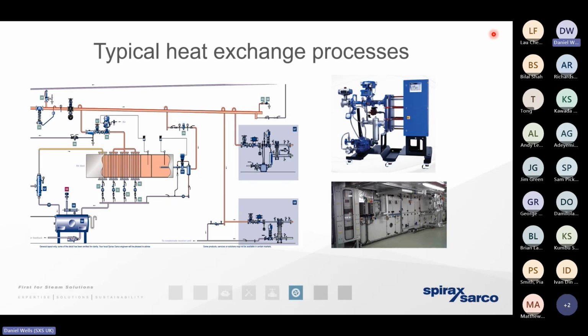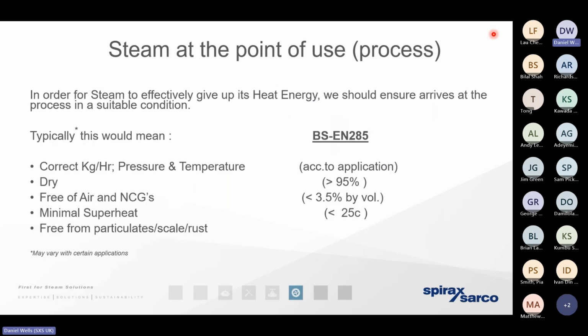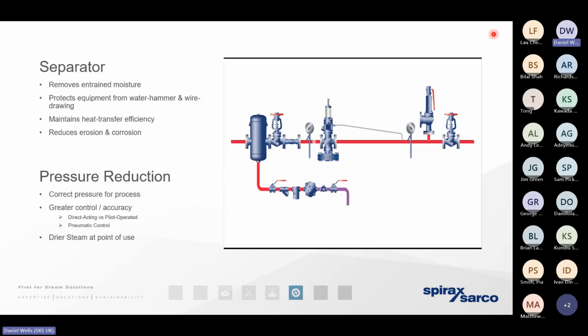More likely, we're going to be using the steam indirectly, which means it passes across one side of a heat exchanger, it heats a process up, and we remove the condensate that is formed as a byproduct to that heat exchange. So this just really reminds us that in future presentations, we're going to look at it in a little bit more detail whenever steam is used directly. It means that we've got a more critical set of criteria to give thought to, because that steam is ultimately an ingredient. We'll cover that off in a little bit more detail in a few weeks' time.